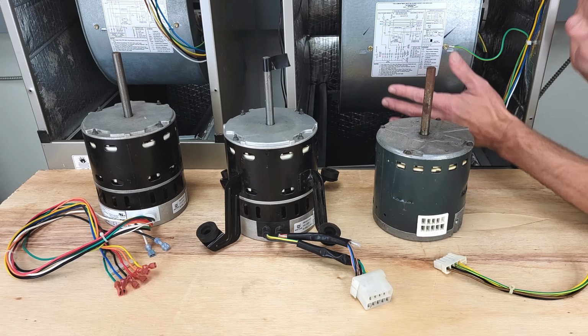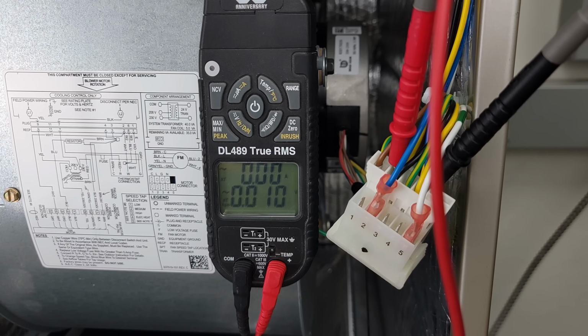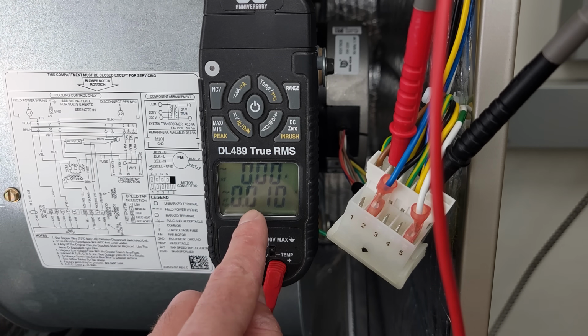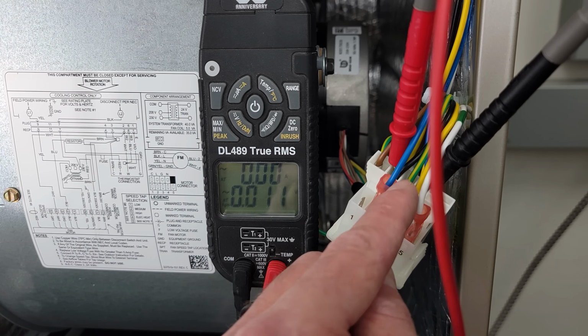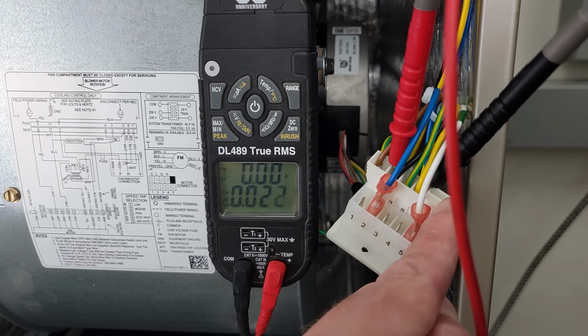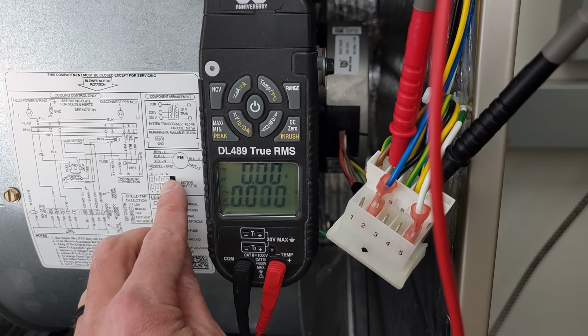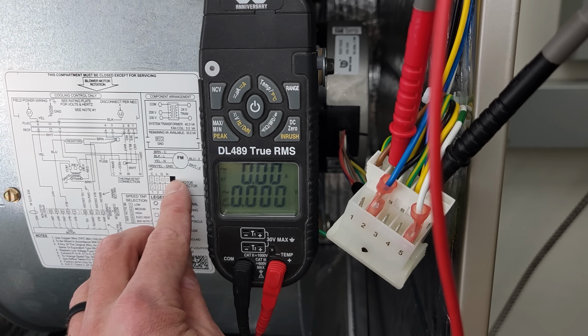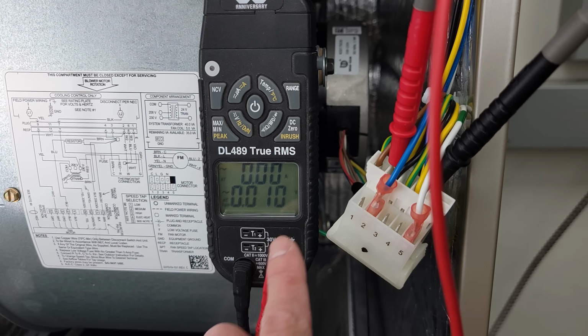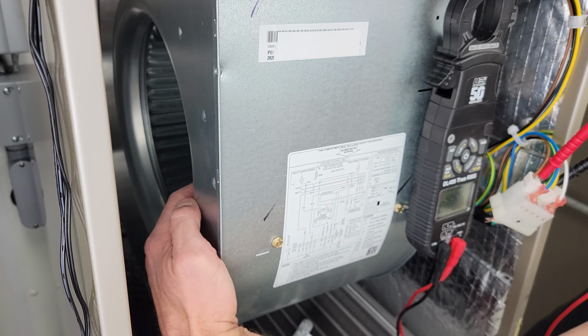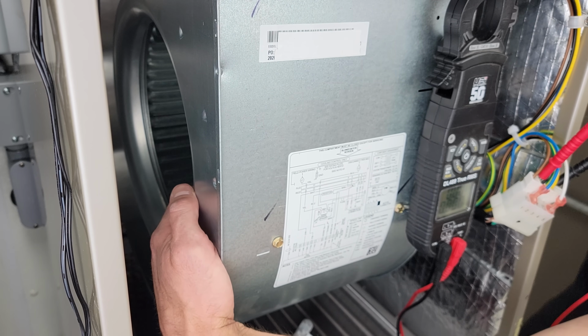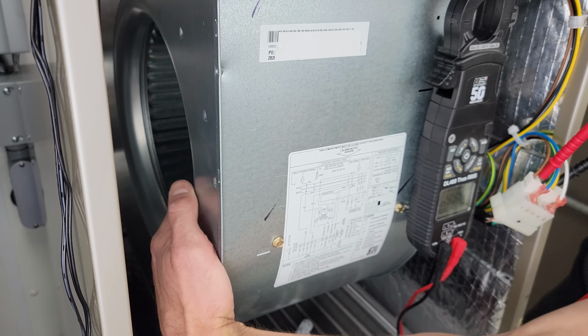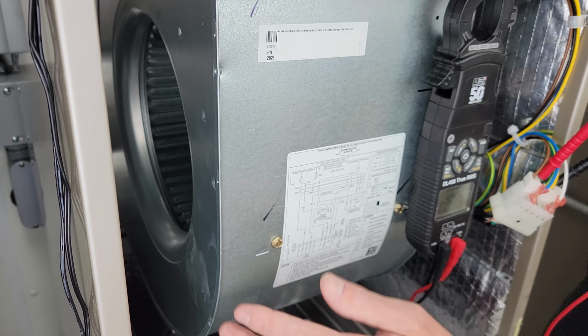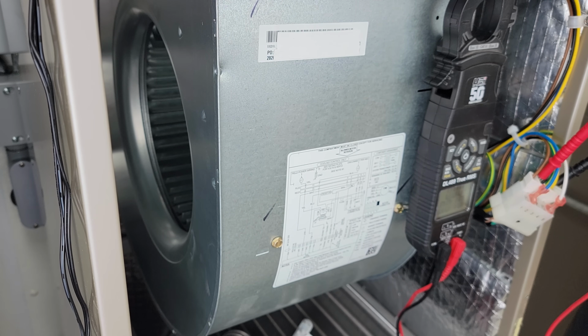You don't have to remove the blower motor in order to troubleshoot these. In order to troubleshoot this, you remove the faceplate, turn the power off, and you're going to check to make sure that you have no power. So right here we have one probe in the L and one probe in the N, as you can see on this wiring diagram right here. And so we verified that we have no voltage, and we want to go ahead and stick our hand right in here and just feel to see if the blower motor is loose or there's some problem right there, maybe it's binding up. And so we can see that that's spinning freely.